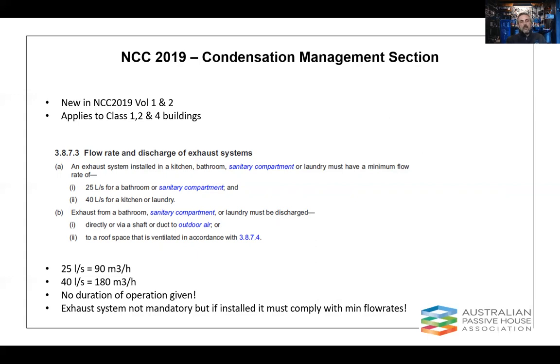That has the consequence of greatly increasing unit size, HRV unit size and cost. It has an over-dehumidification risk because of the high volume of air we're now having to move through the building. It requires extra duct, larger grills, so the impact is fairly extensive and expensive.